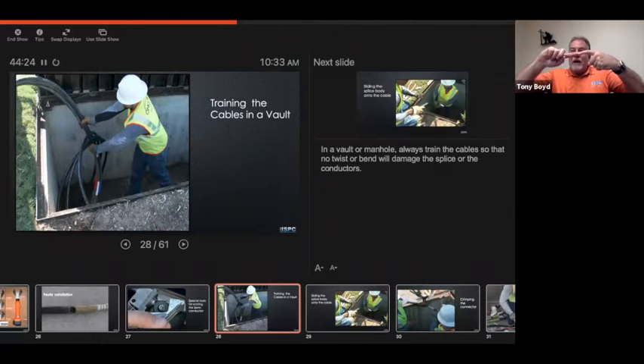Now we splice them together and we go to lay them in a vault, and we untwist the conductor on the inside. I ran several contractor crews back in the day, and I won't mention the years. I've been doing this about 45 years now, so it was way back. And anyway, we had several installations where we installed the cables, made splices, and 2, 3, 4 years later, as load comes in on these cables, because that conductor was twisted as it was laid down into the trench, it made a weak spot inside the splice, and we started having some splice failures.